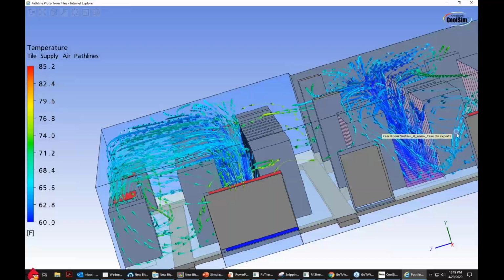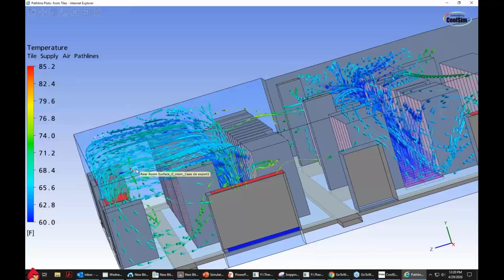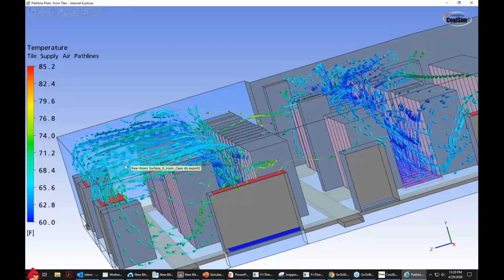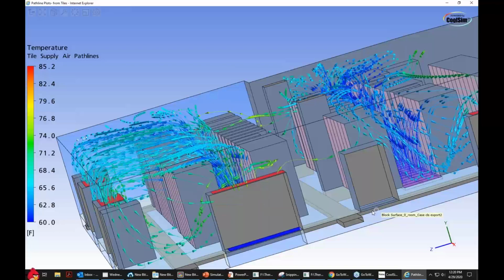This is only supply air. Only the air coming out of these perforated tiles is what should be seen. It should come up and stop right in front of the rack, and it doesn't. It comes up and it blows by. There's too much of it. And you see the temperatures dropping here as we get to the return. So it's actually increasing, right? This cold air is being warmed by the room, really by the output of these racks here.